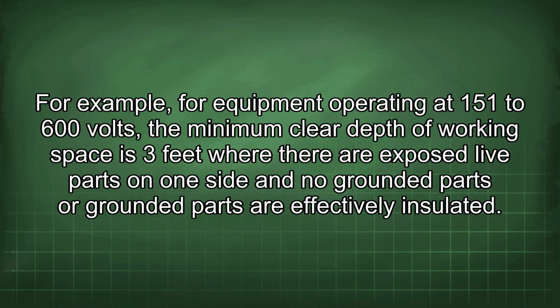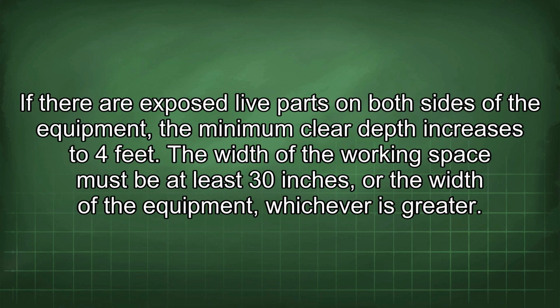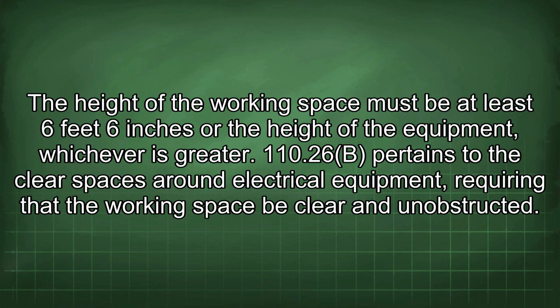For example, for equipment operating at 151 to 600 volts, the minimum clear depth of working space is 3 feet where there are exposed live parts on one side and no grounded parts, or grounded parts are effectively insulated. If there are exposed live parts on both sides of the equipment, the minimum clear depth increases to 4 feet. The width of the working space must be at least 30 inches, or the width of the equipment, whichever is greater. The height of the working space must be at least 6 feet 6 inches, or the height of the equipment, whichever is greater.